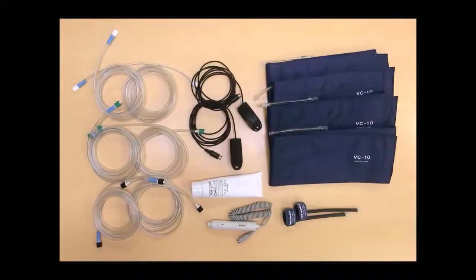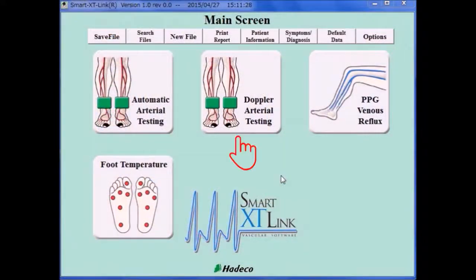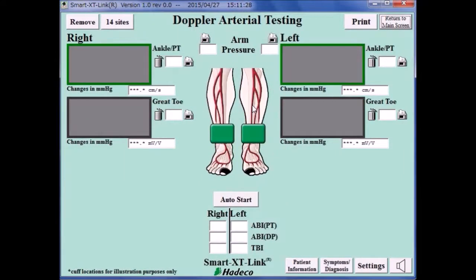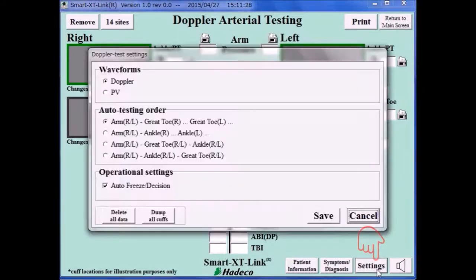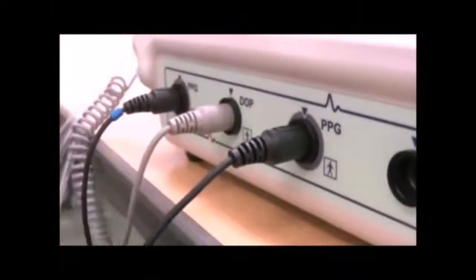Prepare the necessary components for Doppler arterial testing. In addition to the same components for automatic arterial testing, you just need an 8 MHz Doppler probe and ultrasound gel. Click the Doppler arterial testing launcher icon to open it. Click Settings and set each setting for Doppler arterial testing. Select either Doppler or PV to be used for waveform testing. If you select Doppler, connect the 8 MHz probe to the XT.